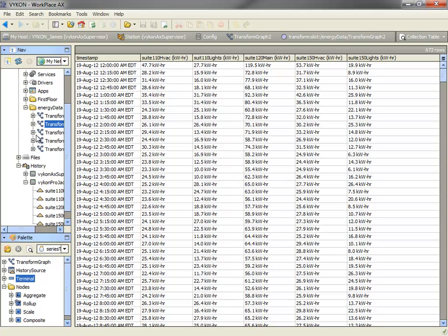In summary, transform graphs allow Niagara users to manipulate series data for reporting purposes. A transform graph requires at least one data source and a terminal node, although it is more likely that transform graphs will be more complex with multiple data source nodes and other nodes for manipulating the data. The transform graph serves as a template to configure the data sources, time ranges, and the schema of the resolved data source. The template is applied at runtime when resolving the transform graph.